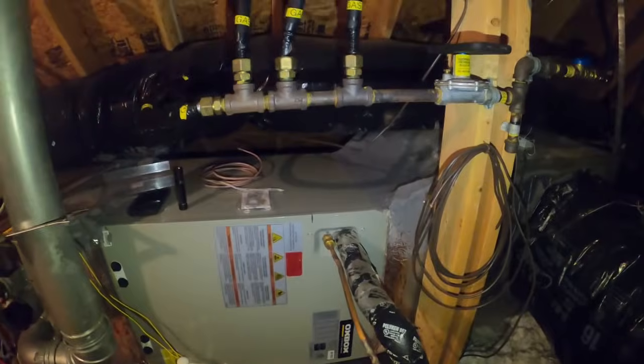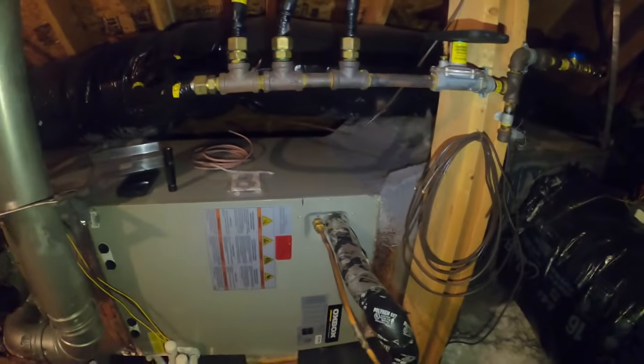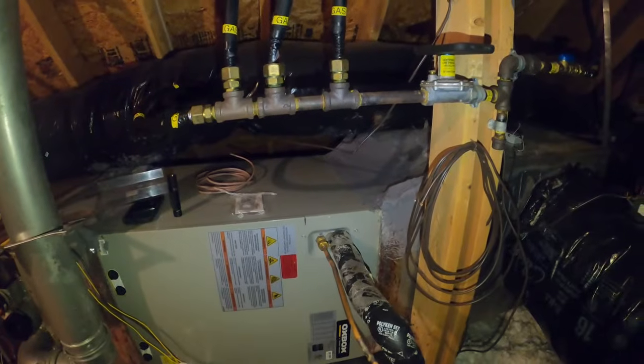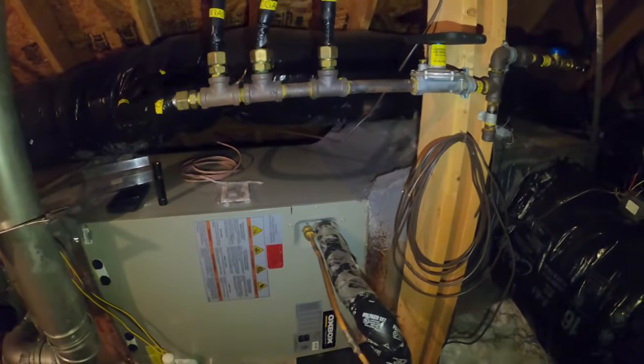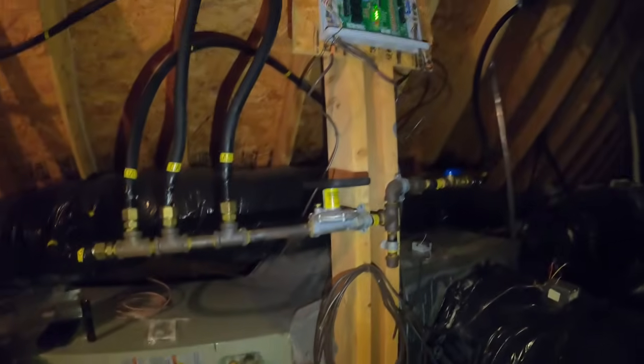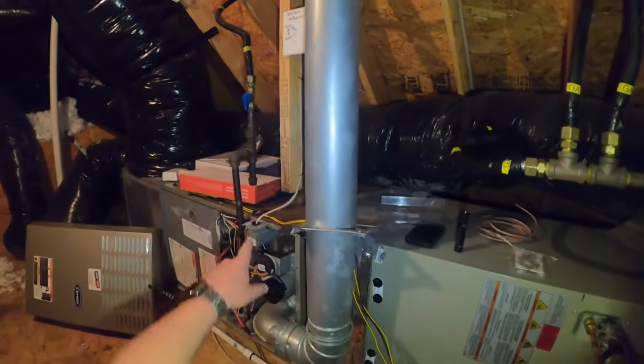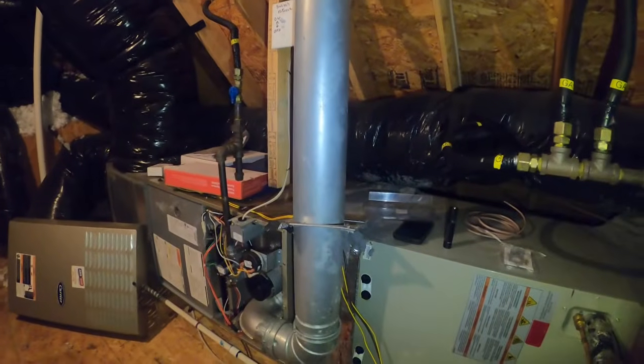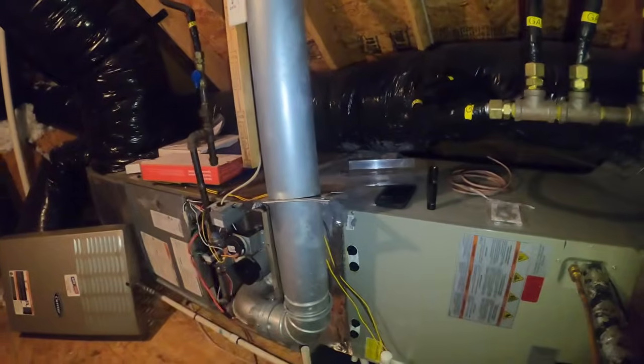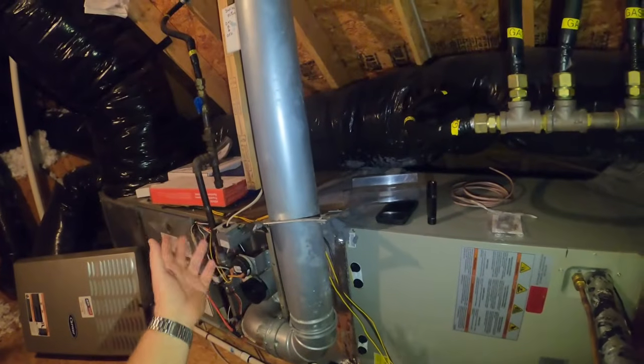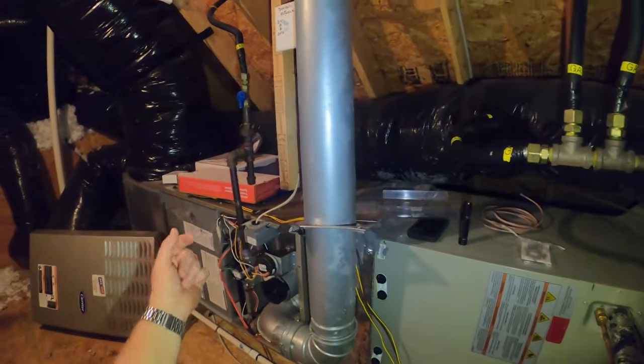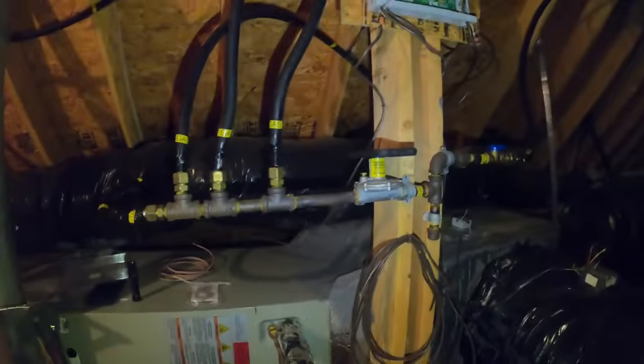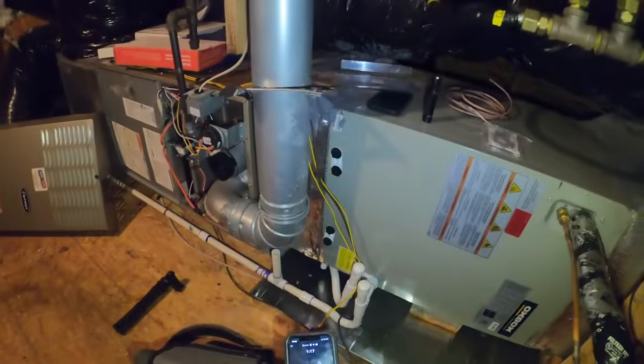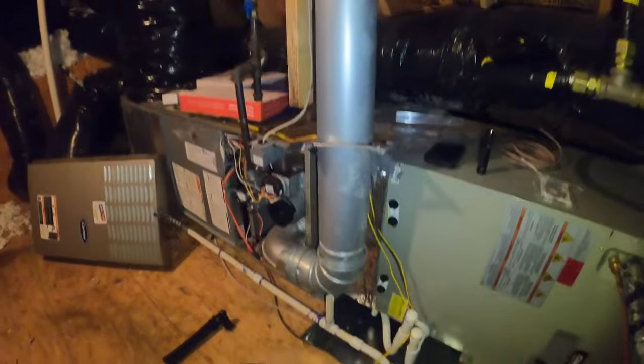You could put a mechanical thermostat on it, run the Y signal through the outdoor temperature switch. When that switch closes, reroute that circuit back in here to start the furnace. But he's got zoning on the house, so we're just going to go ahead and get this set up where it needs to be. So we're going to put in that board over there, which allows us to go in at the 432, which is a 4-zone 3 heat 2 cool board. And it allows you to go in and set up all that stuff for whatever you want. Basically whatever equipment you're looking at, you can do that.